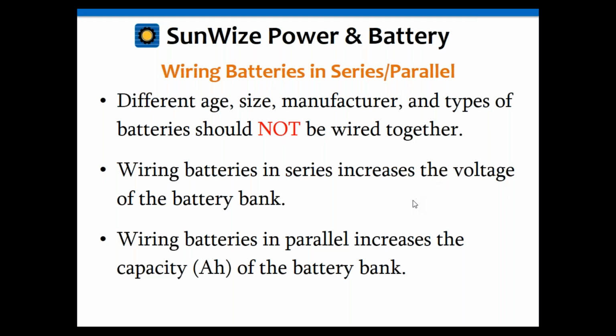When wiring batteries in series, this increases the voltage, and wiring them in parallel increases the capacity. If you've got a 12-volt battery wired in series with another, that gives you 24 volts. If you put 4 of those 12-volt batteries in series, it gives you 48 volts. The capacity works the opposite way: if you have a 100 amp hour battery at 12 volts, and you put a second one in parallel, it gives you 200 amp hours at 12 volts.